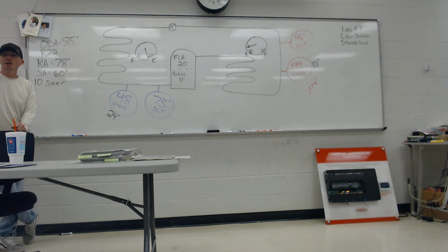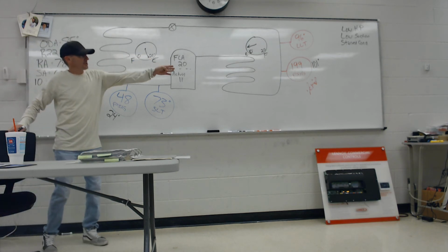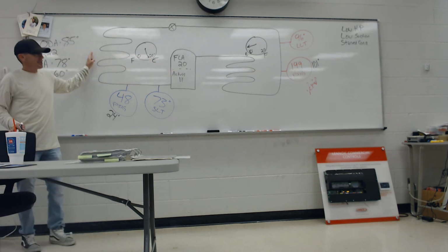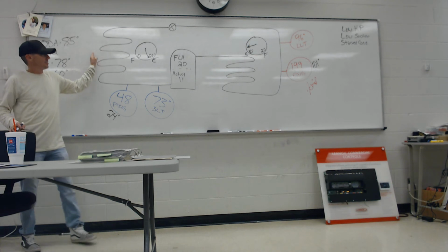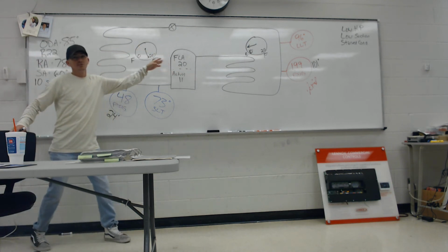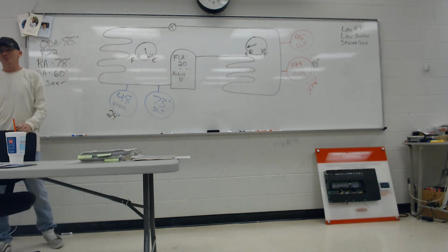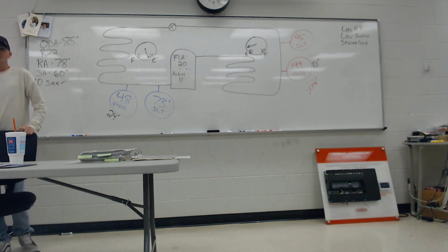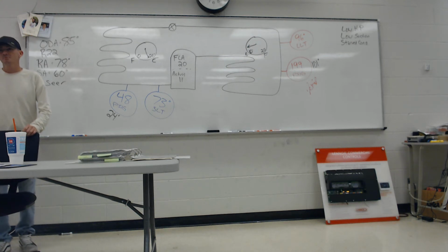So, class, if I have low head pressure, low suction pressure, a starved condenser, and a starved evaporator, what's wrong with it? That's 1,000% undercharged. Low amps too. Everything about this screams undercharged.